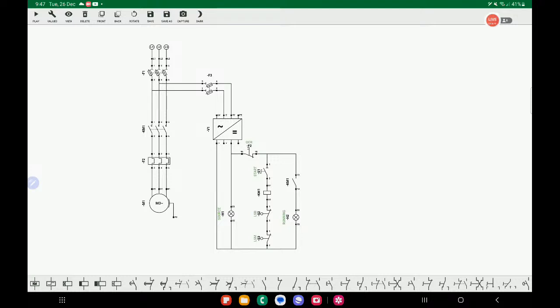So we need to have a winding heater, right? That winding heater will be a protection to our electrical motor. That is, whenever there is inactivity on our remote and our system is not running, the space heater or the winding heater should be activated. What time setting? Normally after 2 minutes or 5 minutes, depending on the makers, whatever they're putting. But normally, based on my experience, it is only 1 minute after inactivity on the system.